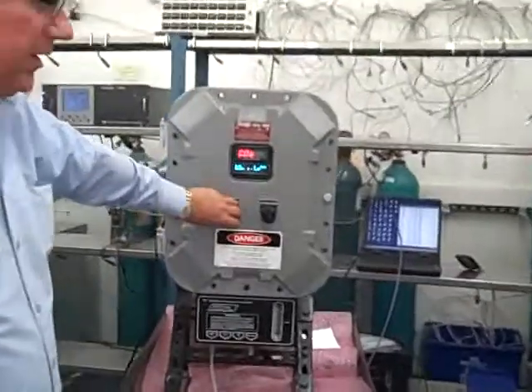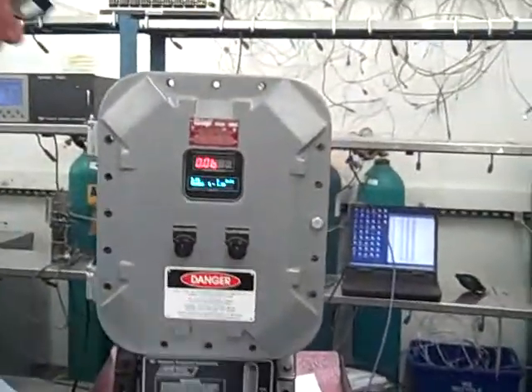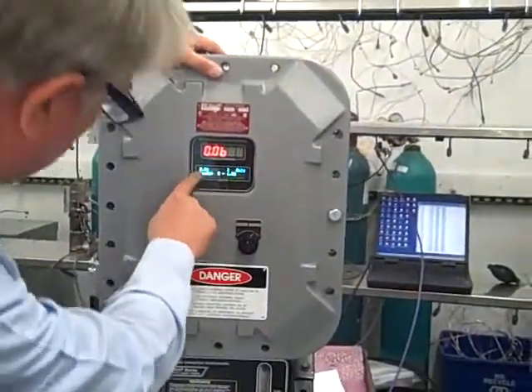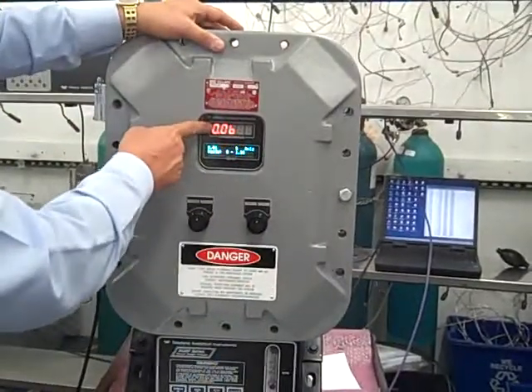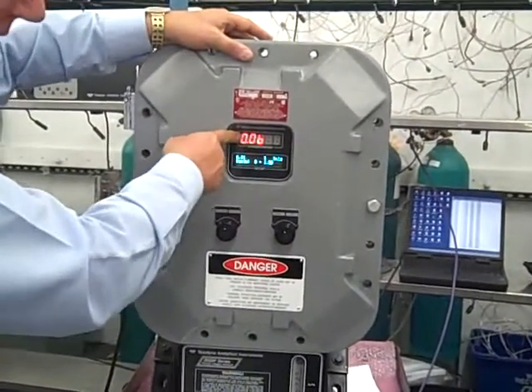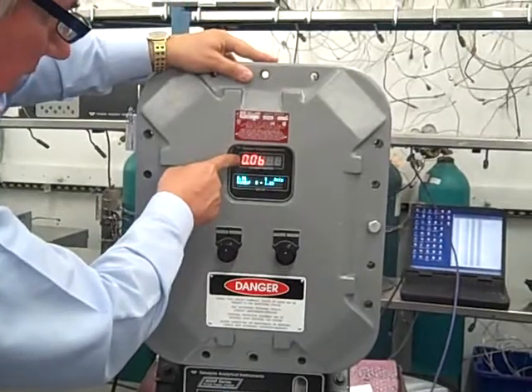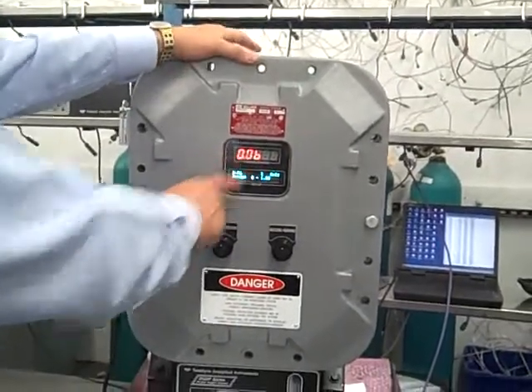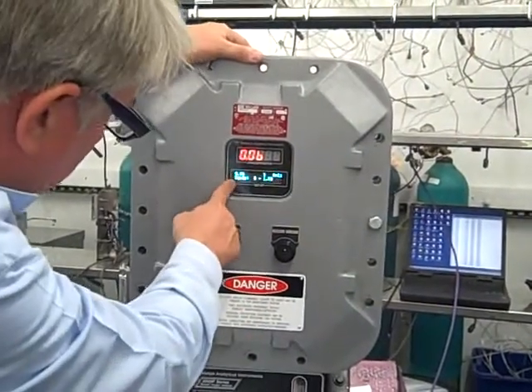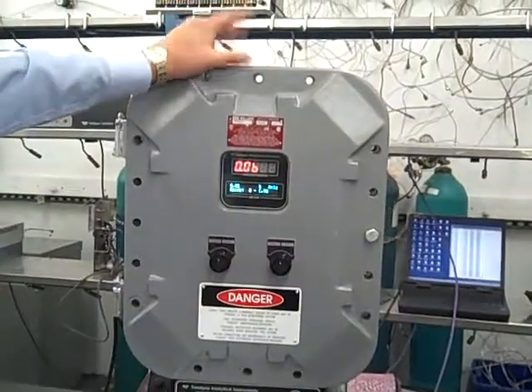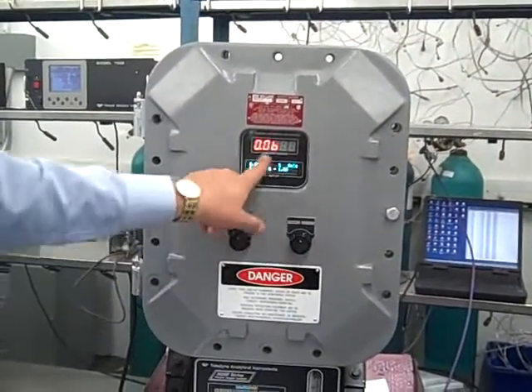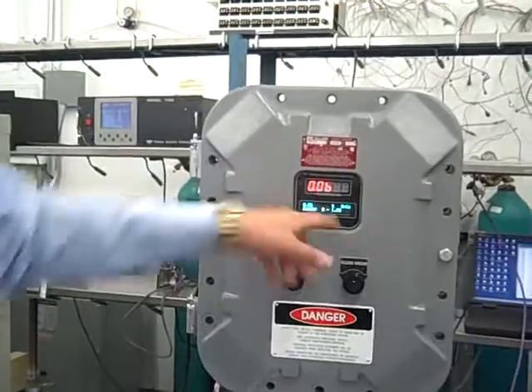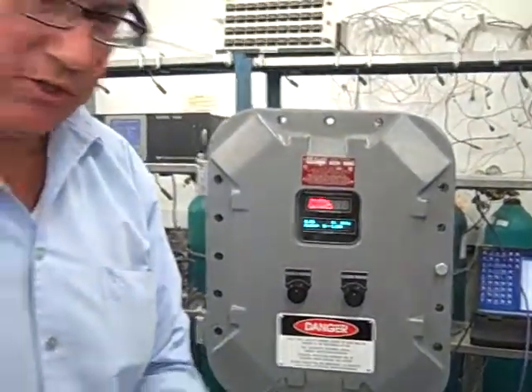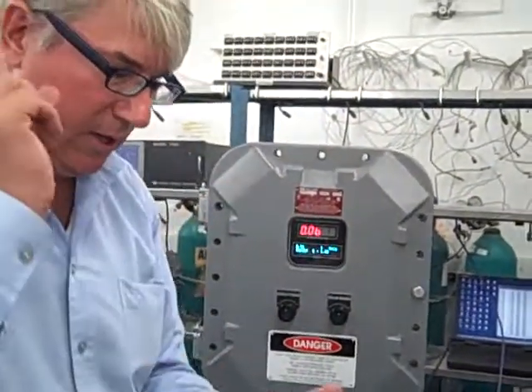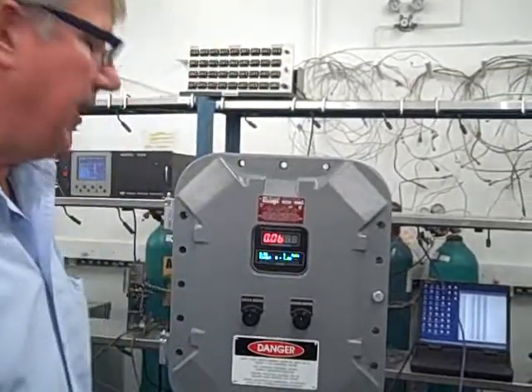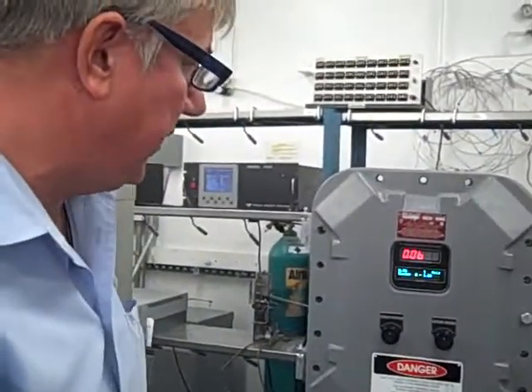Okay, first of all, this is the unit. The controls are mounted on the outside. As you can see, all of the controls, there are two displays. One display is an LED display here, which shows the percent oxygen. In this case, we're reading 0.06% oxygen. This is a vacuum fluorescent display that shows you how to get through the menus of the unit to configure the auto calibration timing, alarm set points, things of this nature. Calibration, gas value, etc., etc.